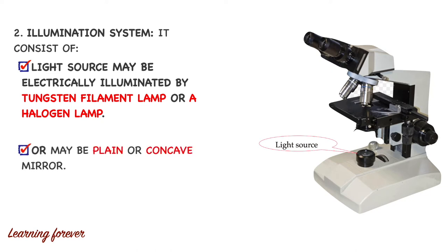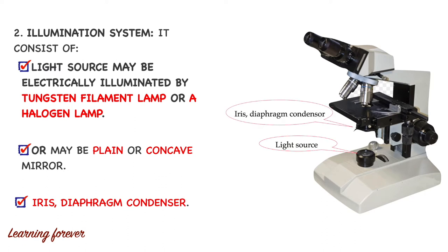Second is the illumination system. It consists of a light source, which may be electrically illuminated by a tungsten filament lamp or a halogen lamp. Most modern microscopes use these artificial lights, whereas student microscopes used in the laboratory do not have an artificial light source — they contain a mirror with two surfaces: a plane surface and a concave surface, which helps to illuminate the object using natural light. The next part of the illumination system is the iris diaphragm and condenser, located exactly below the stage.